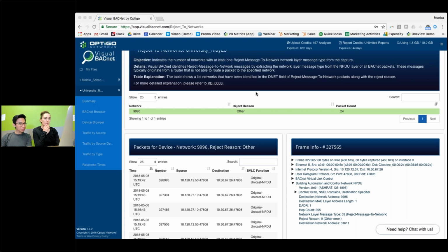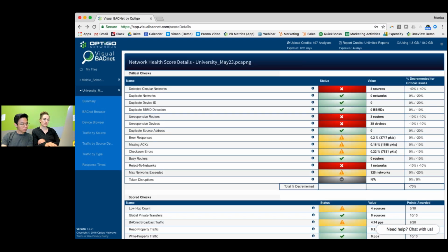It's on a server subnet. One of the other servers is the BBMD on that subnet. This might be a case where we need a bit more information, another capture closer to the source here, so we can see some different information to fill in the rest. Yeah. So we've kind of figured out which areas of the network are problematic, and now we might have to go and I think they actually have quite a few other files and captures that we could probably look through at a later date, but it has focused on the problem, it has focused on the area, so that's a big start. It's a big step in the right direction, and we can keep going down that route.